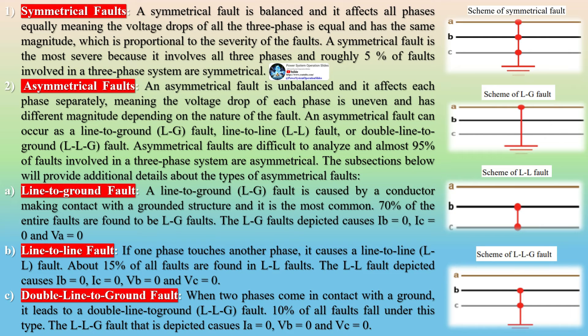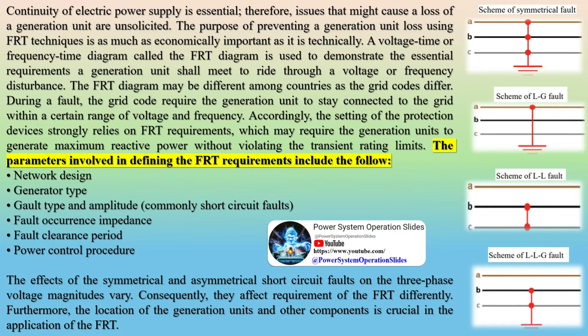Whenever there is a short-circuit fault, the voltage and frequency will decrease while the current will increase in the faulted phase. Accordingly, they can be detected by observation of the current of each phase. Short-circuit faults are the most hazardous as the current is increased to as much as 10 times the nominal current. Short-circuit faults may take an arc form on overhead transmission lines causing the conductor to burn and break if not timely cleared. They may also turn the faulted phase into loads in interconnected systems due to the large decrease in voltage and frequency.